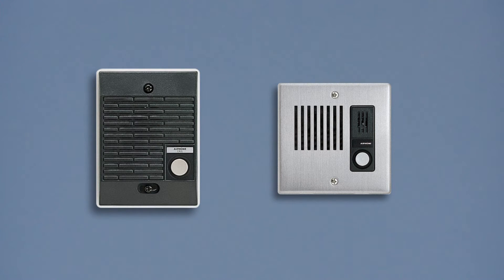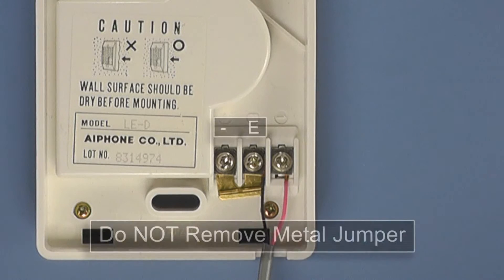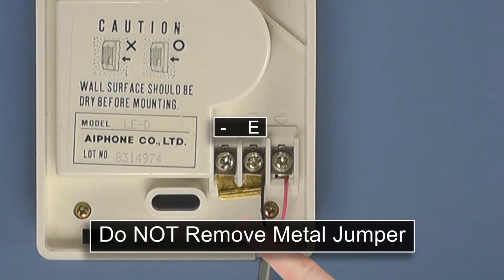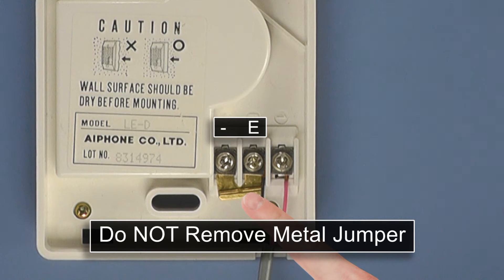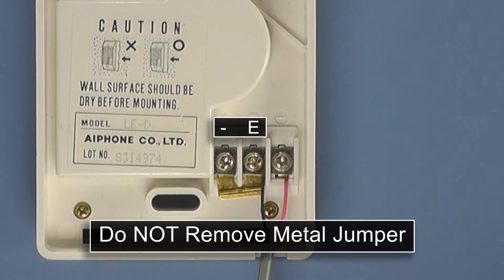like the LE-D and the LE-DA, come fitted with a metal jumper that links the E and the negative terminals together. Do not remove this jumper. Removing this jumper will prevent the door from calling the LEM1DL.